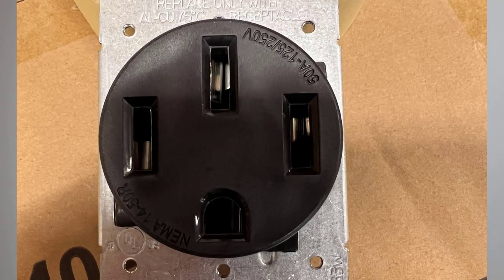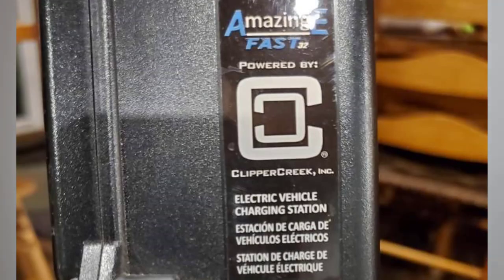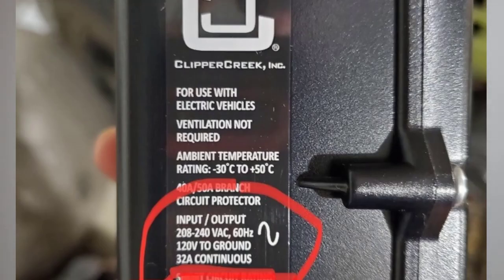This owner installed a NEMA 14-50 outlet in his garage to charge his EV. He thought he did everything right. He made sure that the outlet was UL rated. Even though it is an outlet, he did not regularly plug and unplug the charger — it was pretty much left plugged in at all times. He used a very reputable Clipper Creek charger that only draws 32 amps.